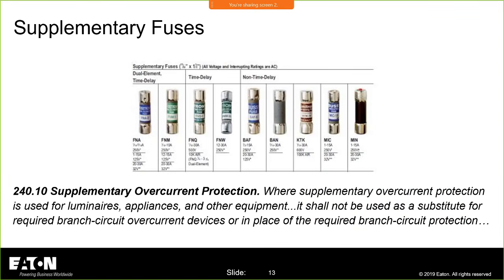And then there are supplementary fuses. Just like there are supplementary circuit breakers, there are supplementary fuses. I believe somebody once told me, when I asked what a supplementary fuse is, that it's a fuse you use when you don't need a fuse, which I thought was very interesting. But these devices are not branch circuit rated. You can't use them to protect a branch circuit.